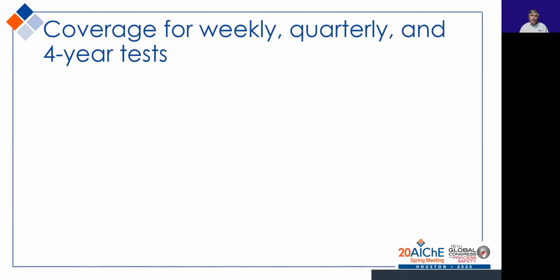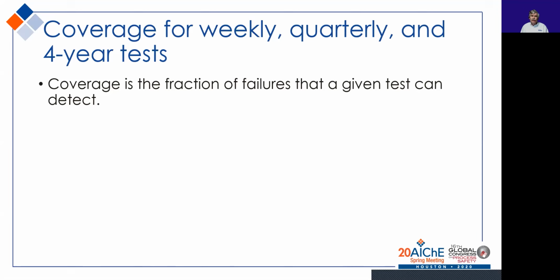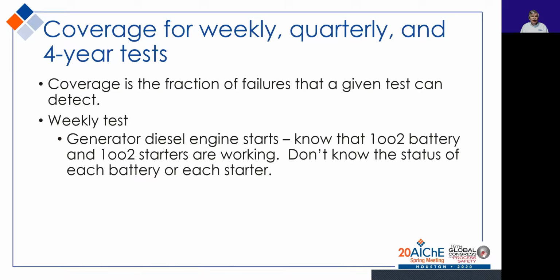Now we come to the coverage for the weekly, quarterly, and the 4-year test. Coverage is the fraction of failures that a given test can detect. In our weekly test, we can detect some failures, but if the diesel engine starts, we know simply that 1 out of 2 batteries and 1 out of 2 starters are working. We don't know the status of each battery or the status of each starter. Battery 1 could work, battery 2 could work, both batteries could work, likewise for the starters.